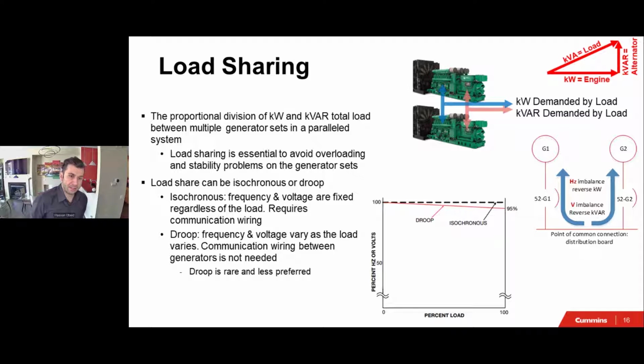Droop, on the other hand, is this red line that you see in here. Your output voltage and frequency will vary as your load varies. For example, at 0% loaded, your frequency might be 61 hertz, you set it up to be that, and your voltage is, let's say, 490. Then when you're 50% loaded, you're at 60 hertz and 480. And then at 100%, you're something lower than that, for example 59.5 hertz.